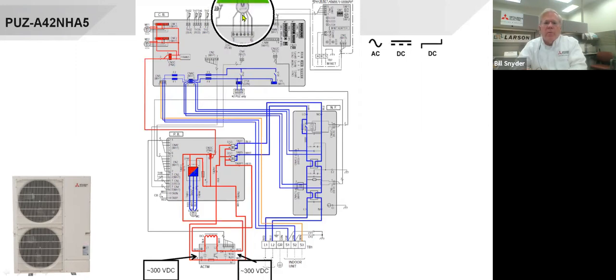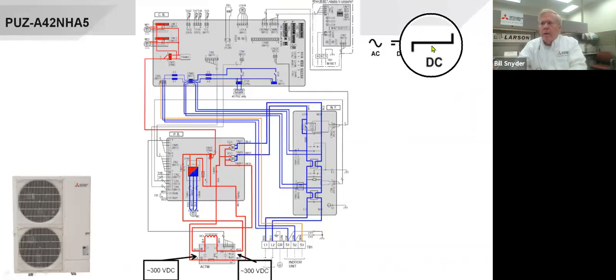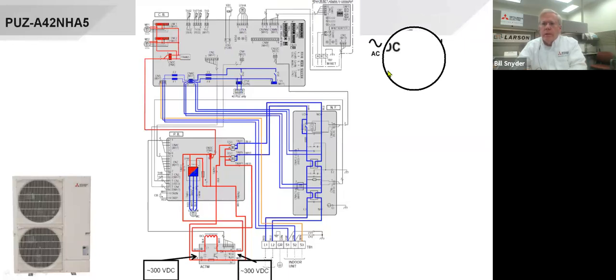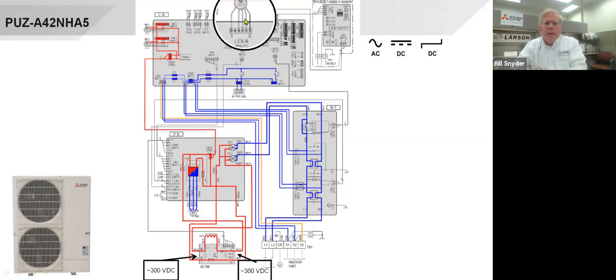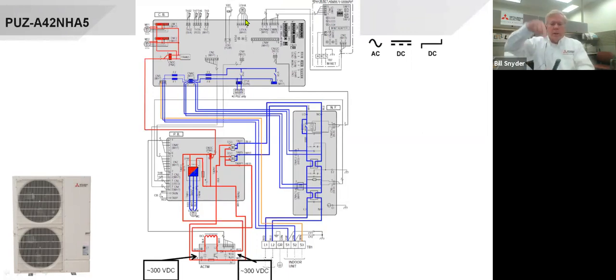is a type of motor. And there's a symbol that looks like that. That's what we're used to seeing for DC. If you see that symbol, that also means DC. So that little motor there is a linear expansion valve. The way a linear expansion valve works is there's a needle valve in the expansion valve, and there's literally a little motor or rotor on the top. Stator, I guess I would call it, on the top, and it turns that needle valve in and out, and that runs on DC. So anytime you see a symbol that looks like that, it's a DC symbol, and you'll see that throughout the boards.